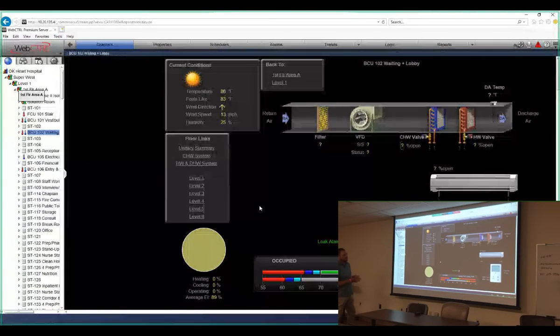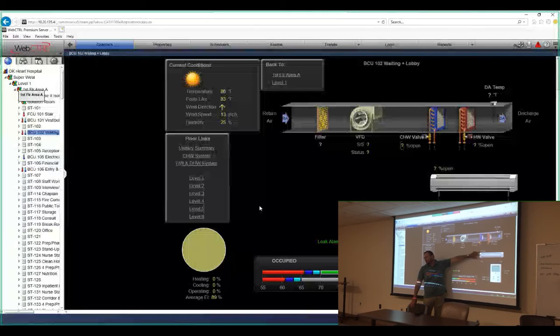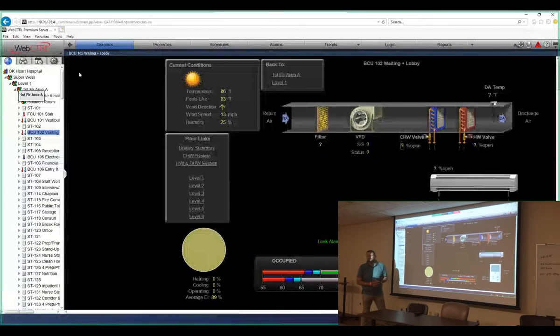This particular blower coil unit has a hot water valve that's controlled to the same thermostat as the radiant heater. So this blower coil unit and that radiant heater valve are going to try to maintain 70 degrees in that space. I believe that's the only unique blower coil unit we have. All of them control the same way. We're monitoring the filter status, start/stop, fan status, chill water valve, hot water valve, discharge temperature, and condensate flow.